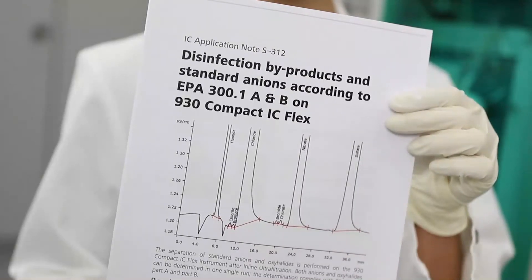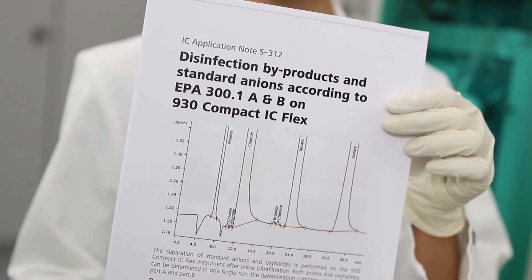The low detection limits achieved comply with standards such as EPA 300.1 A and B, for example. Of course, inline ultrafiltration can be combined with other sample preparation techniques, for example with inline dilution or with partial loop injection. This allows you to configure a fully automated system according to your needs.